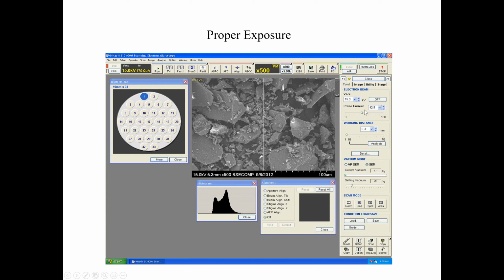Basically now, what's happening here is I'm at 15,000 volts. So when the beam comes in, it's really lighting up these samples here. So it's giving a pretty strong backscatter. The background's the tape. Pretty much everything else is the same shade of gray, so it all has the same chemical composition. But there are a few flecks of the wastewater contaminants that are filtered out. That's what these single white spots are.